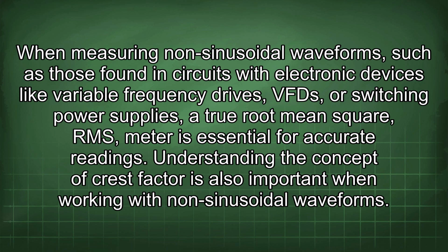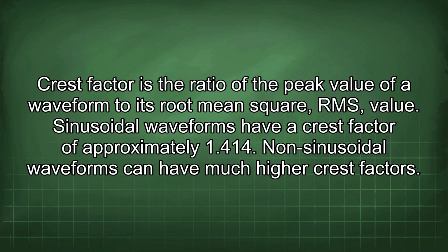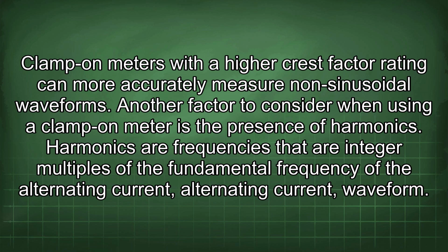Understanding the concept of crest factor is also important when working with non-sinusoidal waveforms. Crest factor is the ratio of the peak value of a waveform to its root mean square (RMS) value. Sinusoidal waveforms have a crest factor of approximately 1.414. Non-sinusoidal waveforms can have much higher crest factors. Clamp-on meters with a higher crest factor rating can more accurately measure non-sinusoidal waveforms.